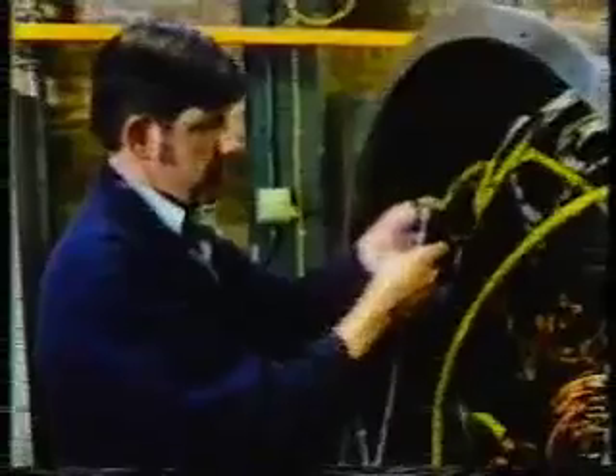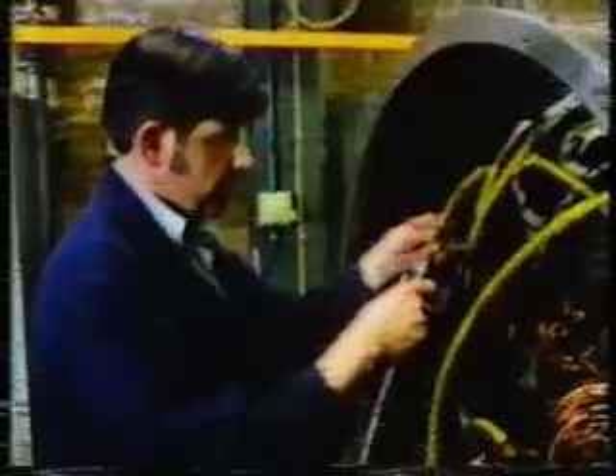The output windings of the alternator consist of copper wire. The standard of insulation is very important. Petbow used Class F materials throughout. The laminated rotor assembly is wound with high-grade wire under constant tension to produce really solid windings, able to withstand the severe centrifugal forces which occur in operation. The number of turns in any one coil is predetermined by the electrical output required.